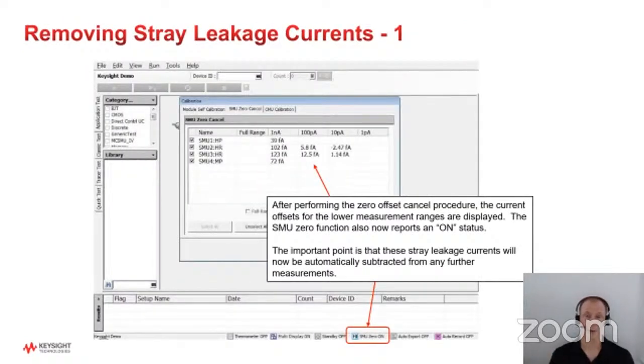On virtually all of our parameter analyzers, there's something called the SMU zero function. What that does is allow you to remove the stray leakage currents automatically. You turn that on, first, of course, with the probe tips up, not touching your devices. It will measure all the stray leakage currents going through the probes and cables, and then it records them and shows them in the table as shown on this slide. Then, when you touch the probes back down on your prober, it will subtract those out. So you get very consistent, clean measurements, only measuring what's actually happening on your DUT and not those stray currents.